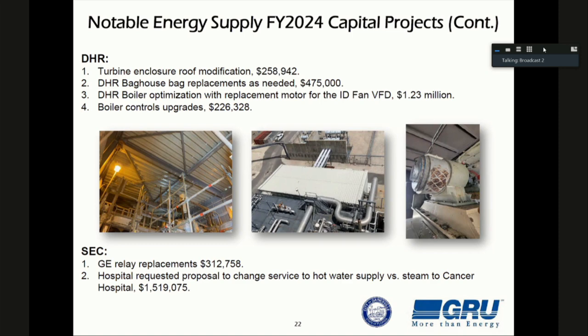So to work on the actual Deerhaven Renewable, we have to physically remove the roof. You see the first two pictures there, the inside of the roof area and the external part of the roof. You have to physically remove the roof to get access to the turbine because the crane has to get above and pull components out. That, by the way, is very costly, it's an extensive amount of work, and it exposes everything inside that compartment to the elements once the roof is removed.